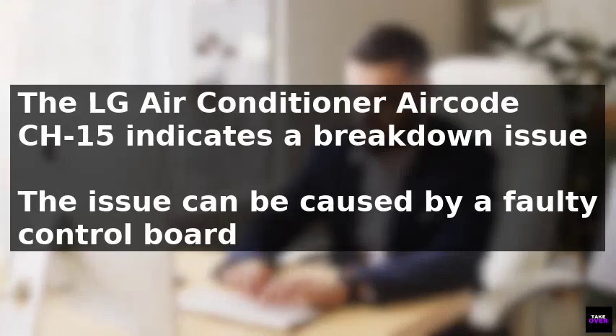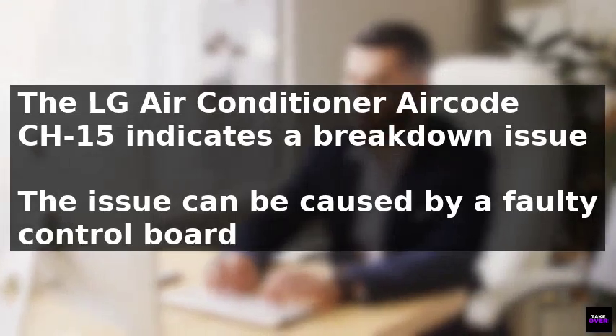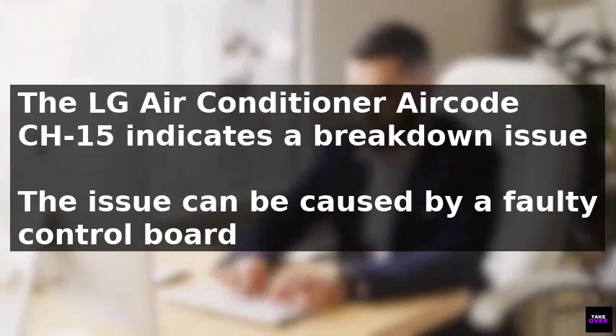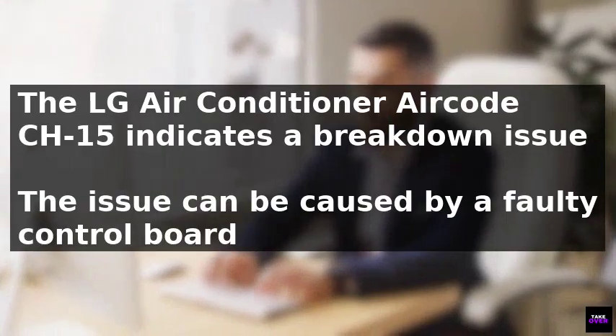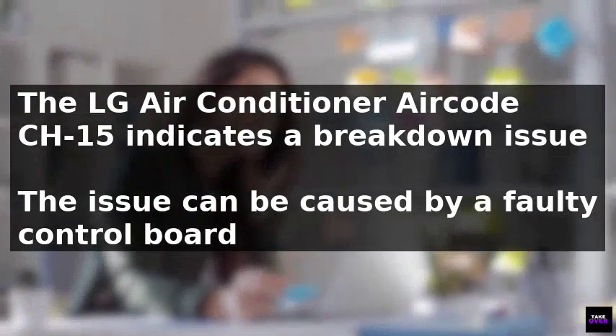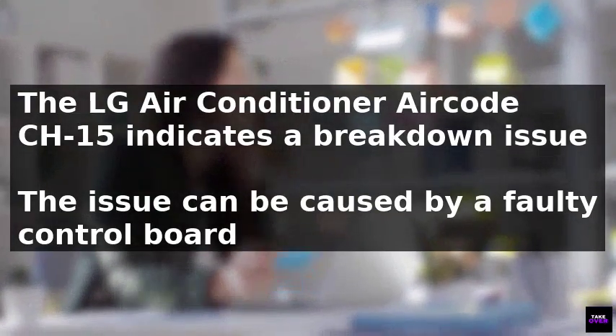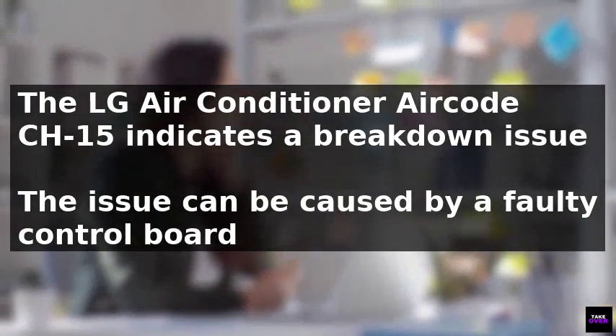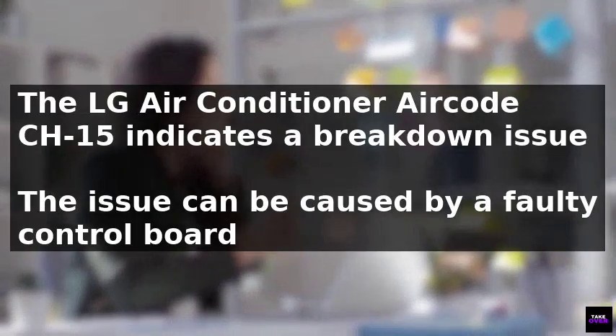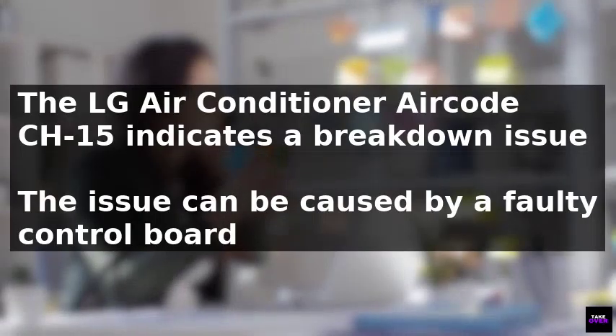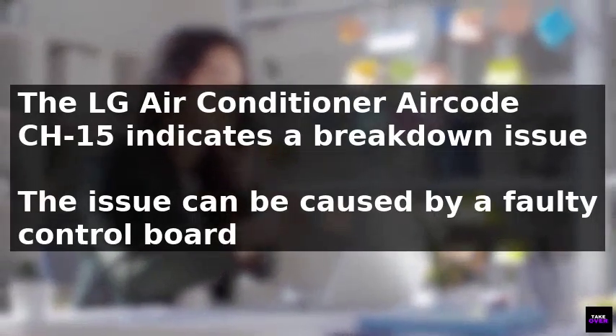The LG air conditioner error code CH15 indicates a breakdown in communication between the fan motor and the control board. This issue can be caused by a faulty control board or loose connections. To resolve the problem, replacing the control board is a potential solution.